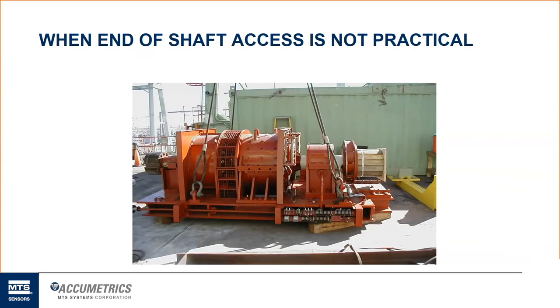Then there are the diode rectification wheels, one for the negative side and one for the positive side of the field. And then it goes down more of the exciter shaft to this coupling flange all the way over to the left-hand side. And this is where the exciter will then couple to the generator itself. So this is typically where we would plan on mounting our next style of EFRM system, which is that mid-shaft style. And we'll go into more detail in the next few slides.